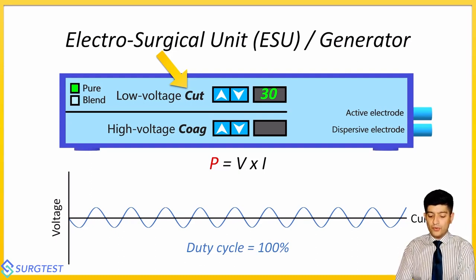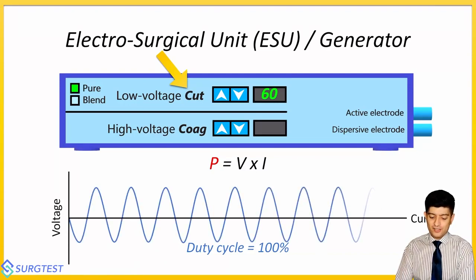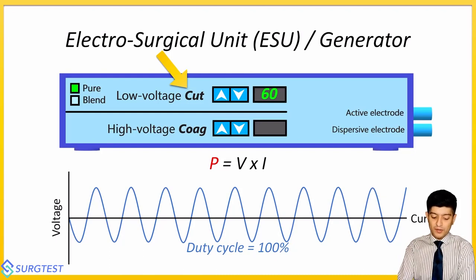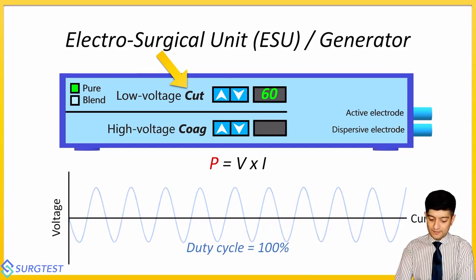Now let's see what happens when you increase the power. I'm changing the wattage to 60. Look at how this curve has changed. We're still at a duty cycle of 100%, meaning the total time the current is flowing has stayed constant. So if power has increased to 2 times, going from 30 to 60, and current (I) has stayed the same because we're at 100%, then the thing that has to increase in proportion is the voltage — which is exactly what you see, as the voltage develops higher peaks on either side of the baseline.